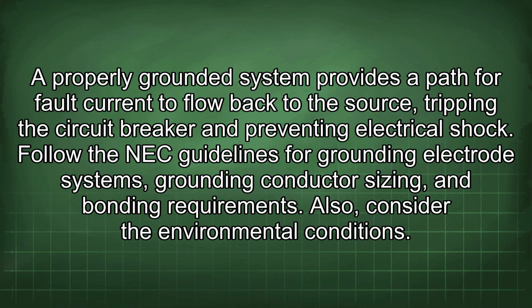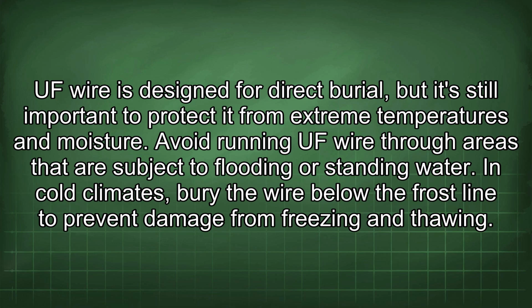Follow the NEC guidelines for grounding electrode systems, grounding conductor sizing, and bonding requirements. Also, consider the environmental conditions. UF wire is designed for direct burial, but it's still important to protect it from extreme temperatures and moisture. Avoid running UF wire through areas that are subject to flooding or standing water.